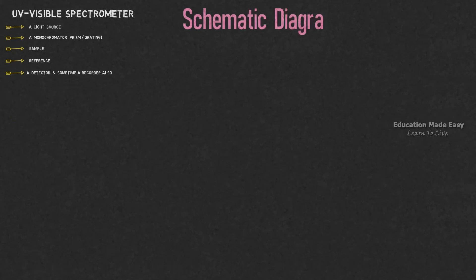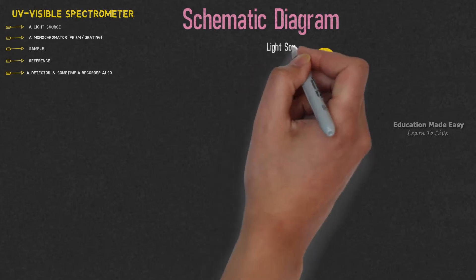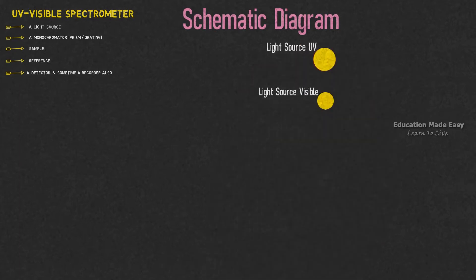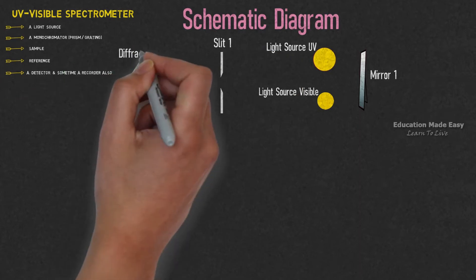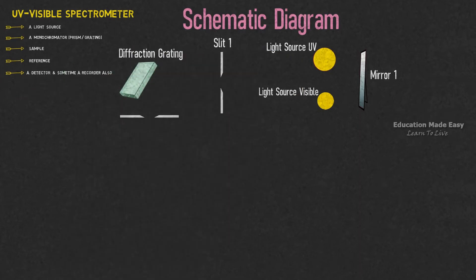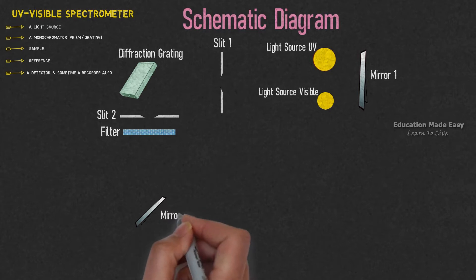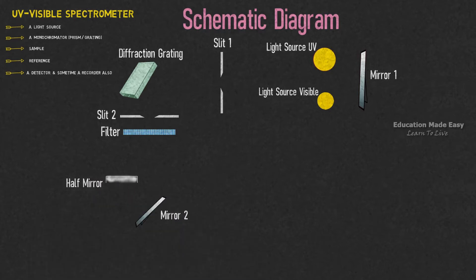Now let us draw the schematic diagram of UV Visible Spectrometer. There are two light sources: light source UV and light source visible. Then we have mirror 1. Next we have slit 1. After the slit we have a diffraction grating. After the diffraction grating we have slit 2. After slit 2 we have a filter. After the filter we have mirror 2, a half mirror, mirror 3, and mirror 4.